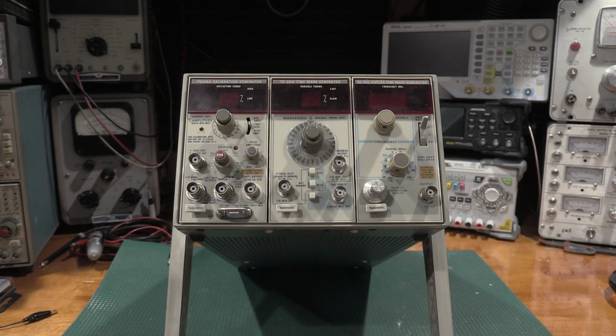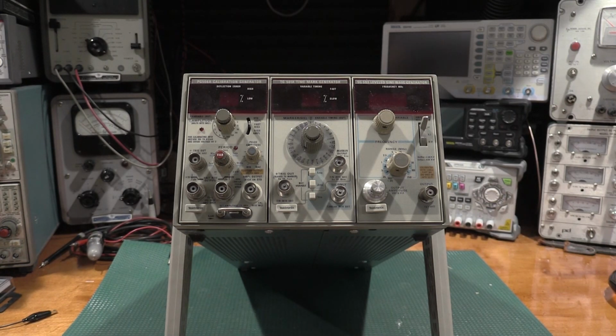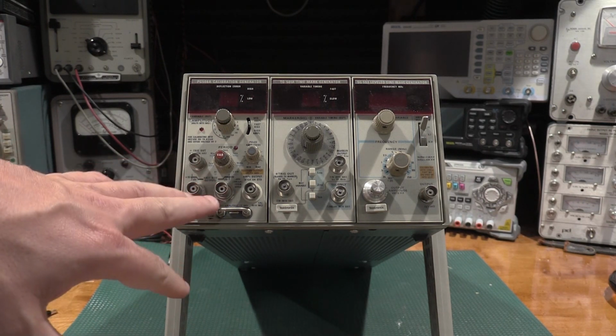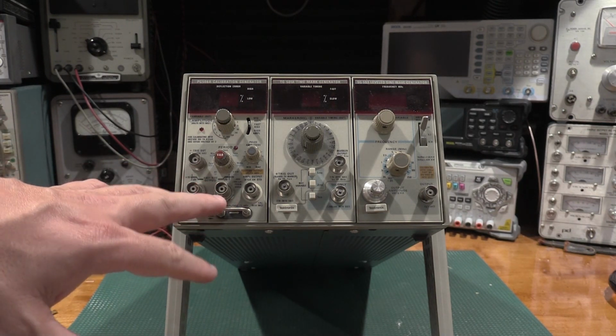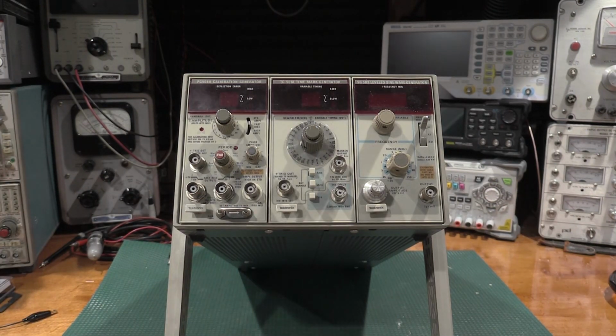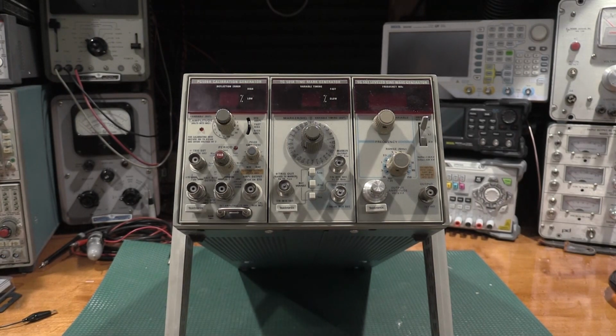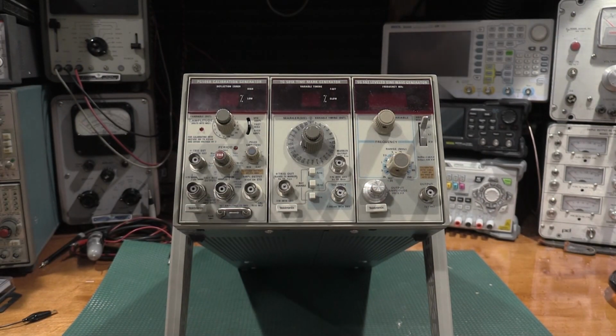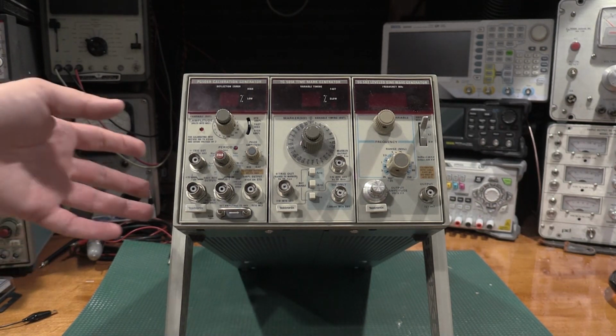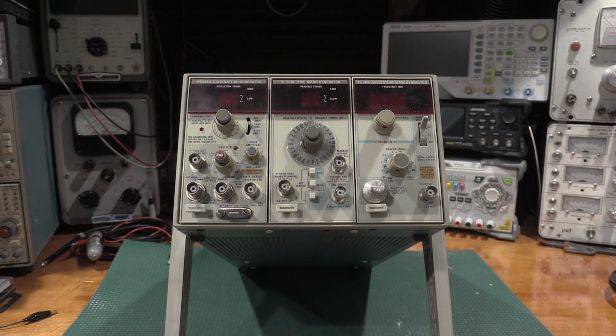These units can get you up to probably a 475A range without stressing too much. The real limitation there is the fast rise, fast fall inputs for doing the high frequency calibration on the vertical amplifiers, and then the SG505 or SG503 runs out of gas at about 250 megahertz. So can't really test it. Can't do a 485, but it can do a 475A. To do a 7000 series, this is enough to do most of the 7000 series vertical plugins.